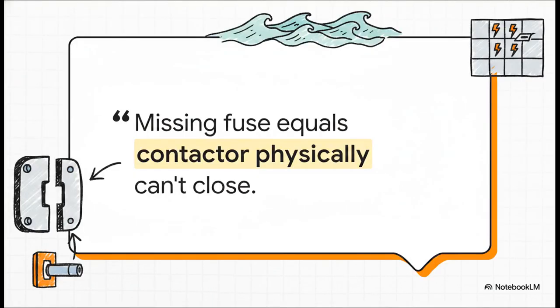Taking that safety a step further, we get to the ultimate mechanical failsafe. A missing fuse means the contactor physically cannot close. Period. The engineers built a physical interlock right into the holder itself. If a tech pulls a fuse for maintenance and forgets to pop it back in, or if one is completely blown out and missing, the mechanism simply locks out. You cannot physically force the contactor to close. It is a foolproof defense against human error, and it protects the entire marine power grid.